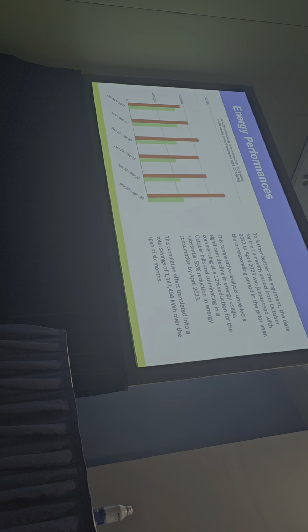It turned out to be, over the course of the entire season, a 55% reduction in energy by April 2023. We predicted a 19% improvement. We ended up with a 55% reduction. Why is that so? Because we're taking advantage of the change in outdoor temperature and always trying to maximize the COP of the system. Now we went from an evaporative condenser on the roof to an adiabatic gas cooler on the roof. Total saving was 1.1 million kilowatt hours over the span of 6 months.